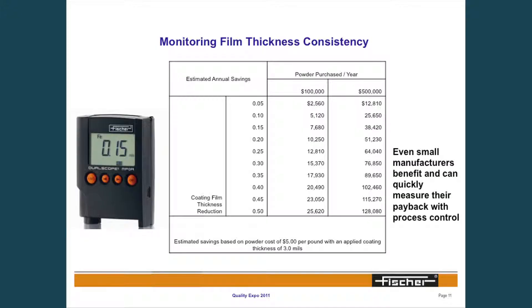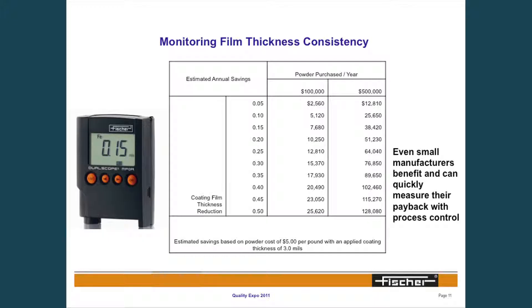I read an article back in 1998 and the light bulb really went off for me as far as why monitoring film thickness or plating thickness is important. It showed that if we control our process by as little as one-tenth of a mil, a $500 investment in one of these instruments could save us $25,000 in a year. In these economic times, controlling material costs could be the difference in whether our companies survive. I've seen a real strong focus on companies controlling their tolerances and process control — this is a good example of what you can achieve with a relatively inexpensive investment in instrumentation.